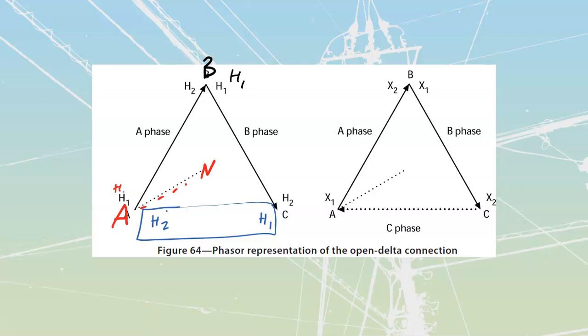Because on my side that I'm supplying, whether it's a step up or step down, since I already have a three-phase line supplied to it, that means I'm going to have two out of the three lines that pass down to the secondary side. So in reality we see these arrows over here and arrows going here, and we see that my secondary or low voltage side is going to have the same arrows.